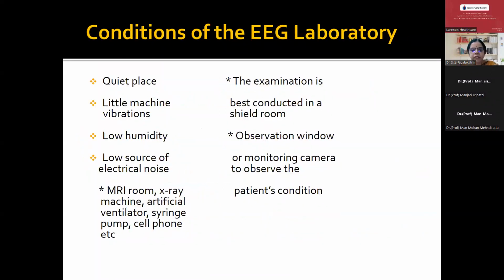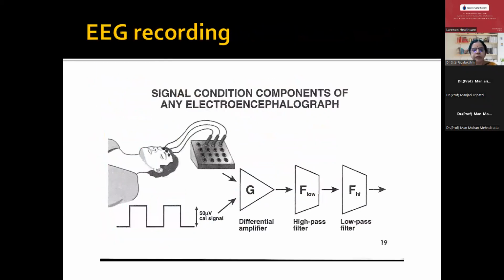So always the EEG recording should be done in a quiet place with little machine vibrations. Humidity should be low, so always the AC should be on. Low source of electrical noise. It should be away from the large AC units of the hospitals. It should not be close to any MRI or X-ray machine. And the examination is best conducted in a shielded room if possible. There should be an observation window for the technologist to see or monitor the camera.